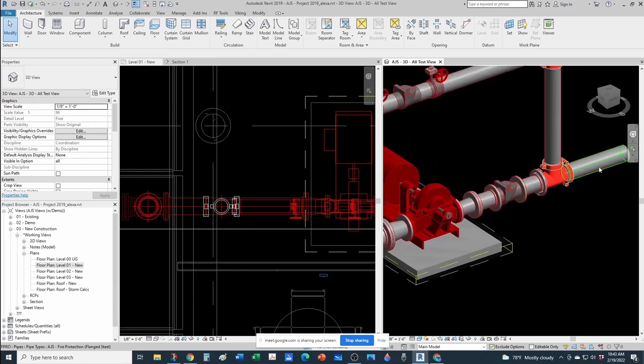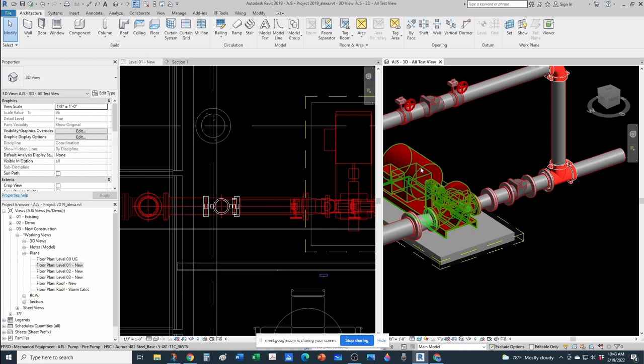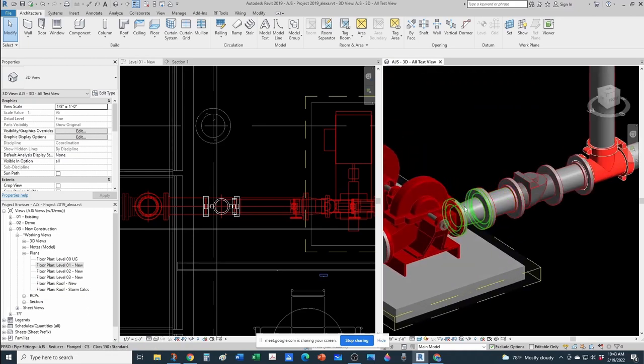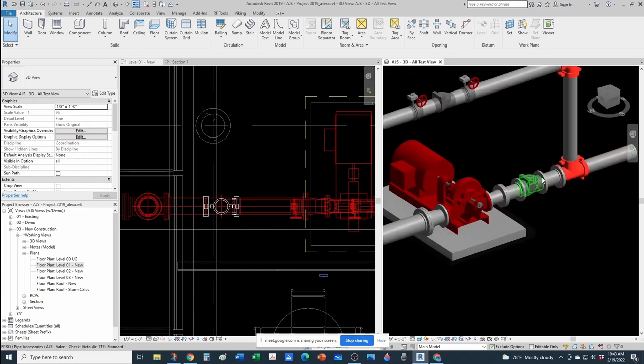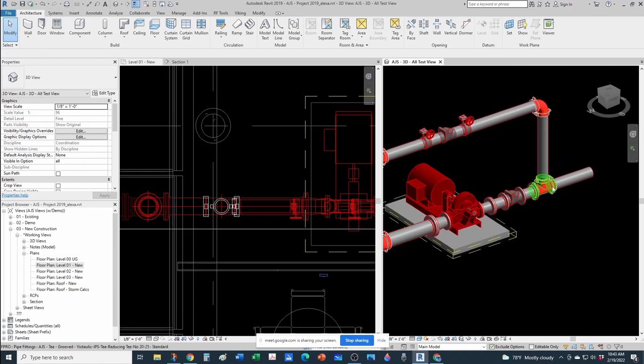In this case, it was a 6-inch pipe because this is a 1000 GPM pump. So we do need the increaser. Then we have our check valve here, which can be grooved or flanged, and then we connect back with our bypass. Now, one thing to keep in mind is that if we're gonna have a test header, that test header has to be prior to your connection of the bypass. That's not really a requirement, it's a recommendation by NFPA 20, but we're gonna follow it.